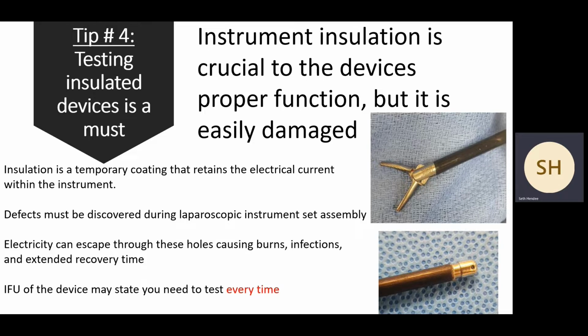Tip number four, testing insulated devices is a must. Okay, this didn't have its proper due in AAMI as far as I'm concerned until 2020. We used to say that this was a performance testing process, just like testing a scissor to make sure it cuts, because that is the function of a scissor. We would say that you should test the insulation on a coated device, because part of the instrument's performance is that the insulation is intact. But in 2020, there was a new amendment to ST79 that specifically called out insulation in electrosurgical devices and said that it should be tested each time, because these are a true patient safety risk when they have issues.